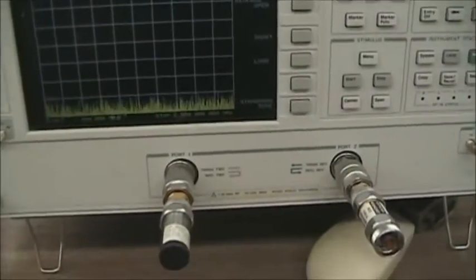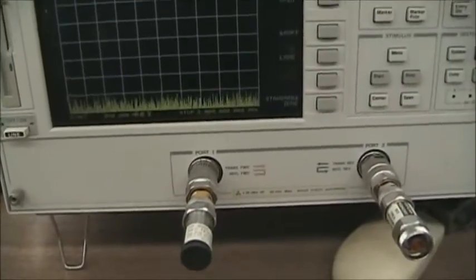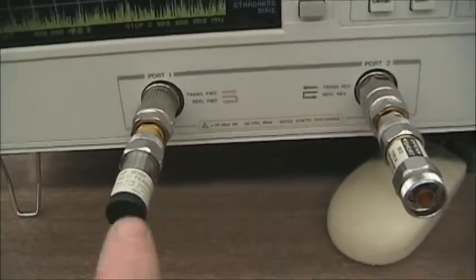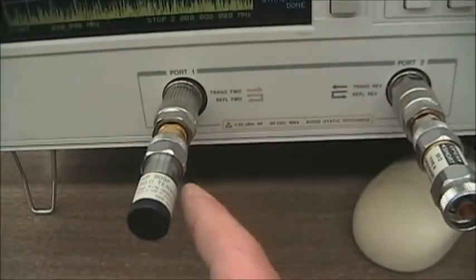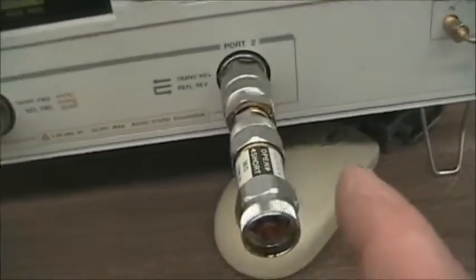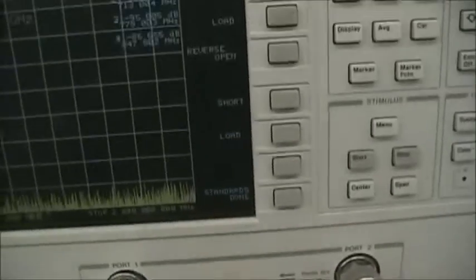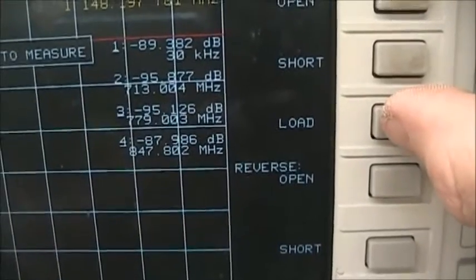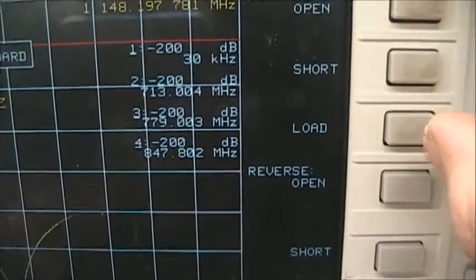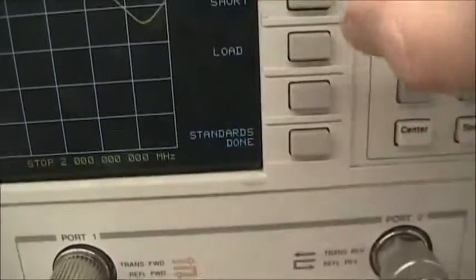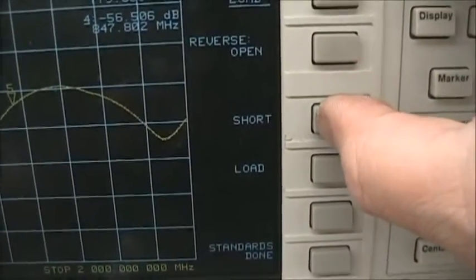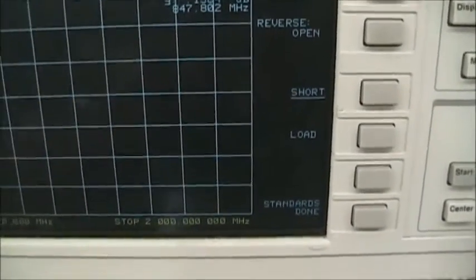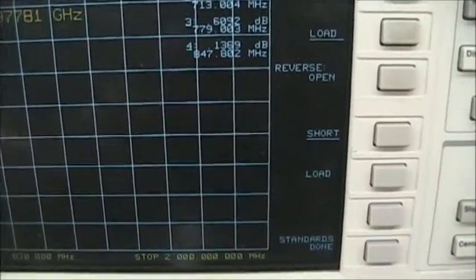I have removed the cable and filter, and now I have my calibration loads on the network analyzer. On port one, I have the 50 ohm load. On port two, I have the short. Now on the forward port, which is where the 50 ohm load is, we just press load, and on the output, we'll push short because we have the short on the output. Now we're simply going to go through and do short open load on both ports.